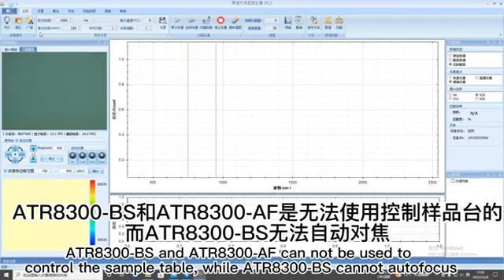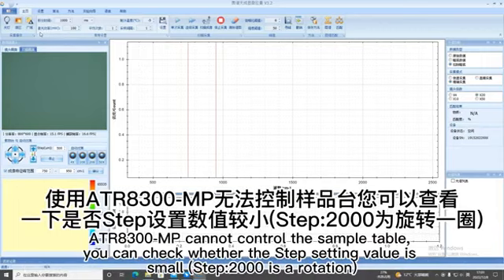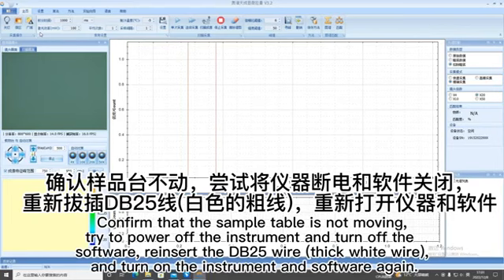ATR8300BS and ATR8300AF cannot be used to control the sample table, while ATR8300BS cannot autofocus. ATR8300MP cannot control the sample table. You can check whether the step setting value is small; 2000 is one rotation. Confirm that the sample table is not moving. Try to power off the instrument and turn off the software. Reinsert the DB25 wire, and turn on the instrument and software again.